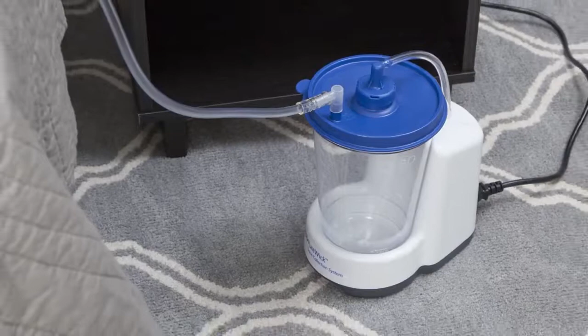For optimal results, place the PureWick Urine Collection System on the floor. The PureWick Urine Collection System should be stationary while in use. Device is not designed to be used while in transport. Caution: avoid creating a tripping hazard with the collector tubing or power cord. Plug the PureWick Urine Collection System power cord into the device inlet and then into an AC power outlet. The device should be positioned for easy access to the AC inlet and power cord. Make sure the power switch is turned off before connecting the power cord.